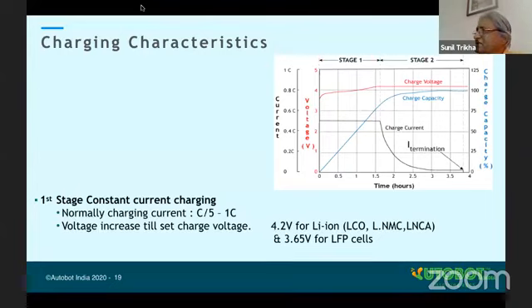These batteries are charged in two stages. The first stage is constant current charging. The battery is charged at a C/5 or 1C rate, meaning a 100Ah battery can be charged at 20 amp to 100 amp, up to a certain threshold voltage. For NMC or NCA, this threshold voltage is 4.2 volts, so up to 4.2 volts we give constant current charging.